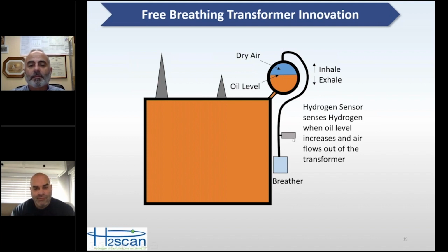And so some people are now putting hydrogen sensors on that breather tube. As the gas is coming out of the transformer, typically with a free breather, you don't want to measure hydrogen in the oil because the hydrogen will escape very quickly. But if you're measuring hydrogen where the gas is escaping from the transformer, then you can catch that, and you'll know if your free breathing transformer is generating hydrogen or not, because typically the hydrogen is going to bubble up and escape before much of it dissolves in the oil. So in a free breather, if you're going to monitor in the oil, you're probably not going to see hydrogen very often.